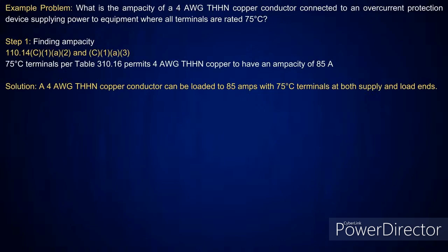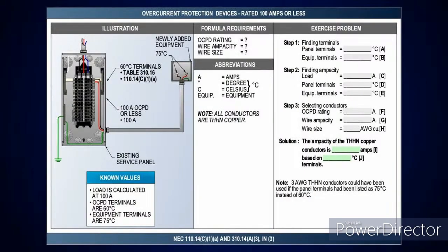Everyone needs to learn that. Now let's change it a little: if I'm coming from the panel rated 75°C, but going to an old motor rated 60°C, then I need a breaker rated 60/75°C and I use the 60°C column. And if those terminals are unknown, you also default to 60°C. Here's the illustration: the panel board is rated 60°C but the newly installed equipment is 75°C — so which column do you use? You're going to use the 60°C column. These are the things to point out based on what you're connecting to.